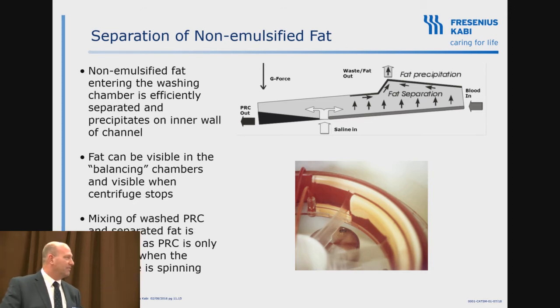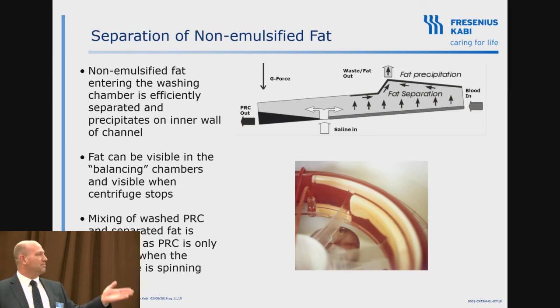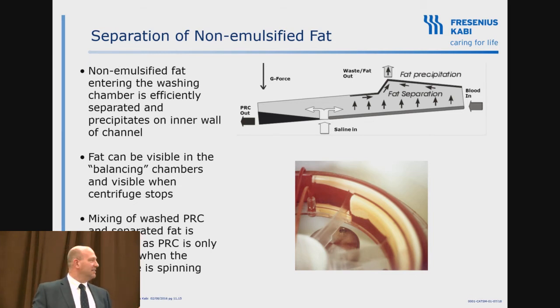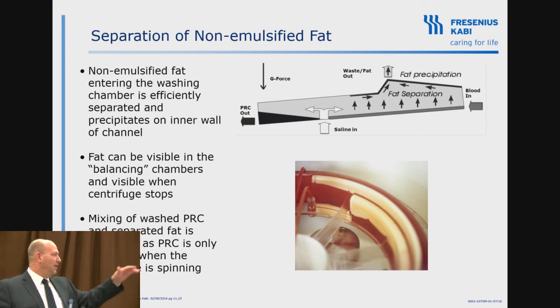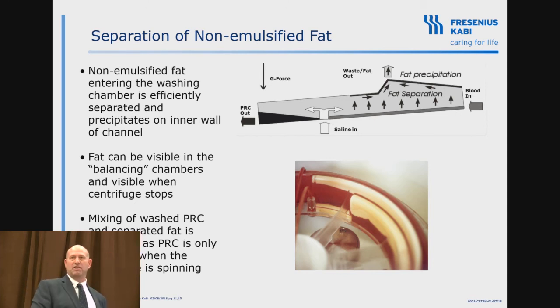On the top there, that's what I call the linear view. Our chamber is a double spiral. So if you take that and you straighten it out, and you look at the centrifugal force, you're looking down at it, the centrifugal force pushing down, so the blood's going to come in. On the right-hand side there, everything lighter goes out into the waste port, plasma, fat. Red cells march down, come to the saline port. Saline resuspends those red cells that were packed at about 80% to about 15 to 20%, then pushes that saline retrograde, or the waste retrograde, up to the waste port.